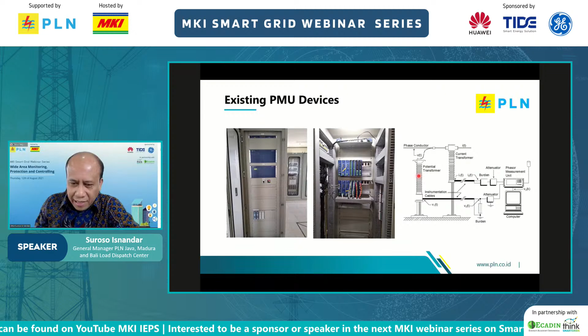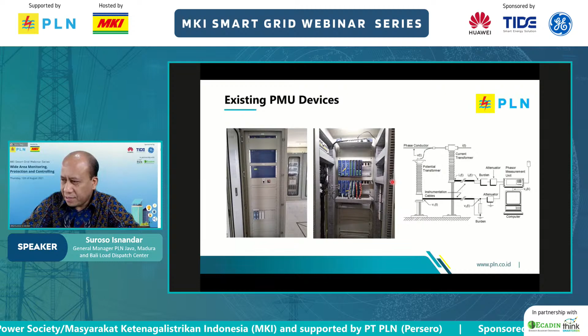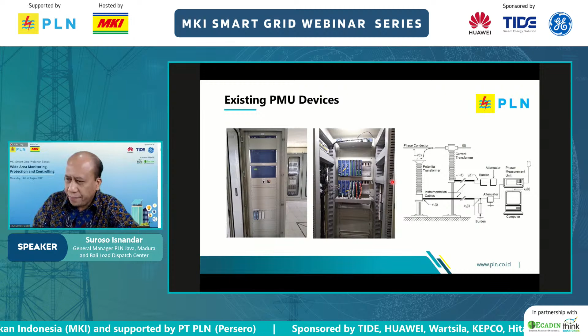And the existing PMU configuration where the current and also the voltage reading are taken from the field, from the substation, from the current transformer, and also from the potential transformer. And through the PMU, Phasor Measurement Unit, will be sent into our server on the Java Control Center. And on top of this, we also access the PMU function within the DFR, Disturbance Fault Recording Relay, based on the standard of IEEE C37.118, which is actually the IEEE standard for synchrophasor on the power system.